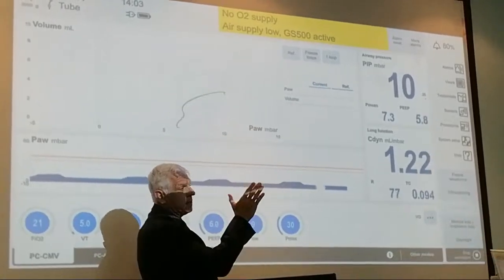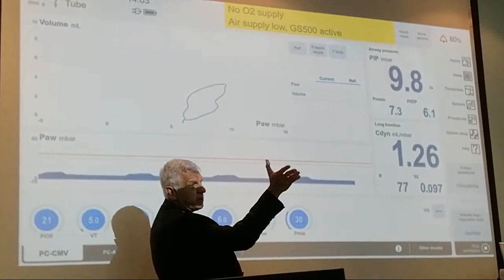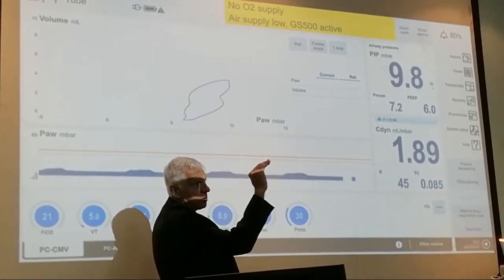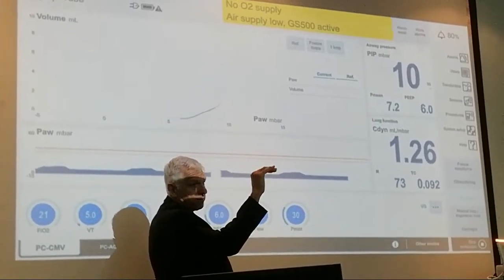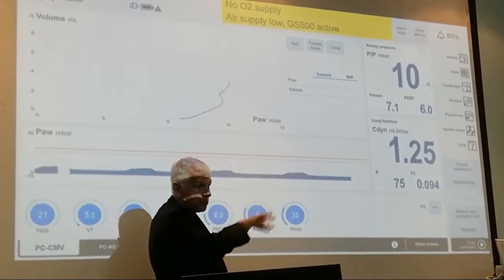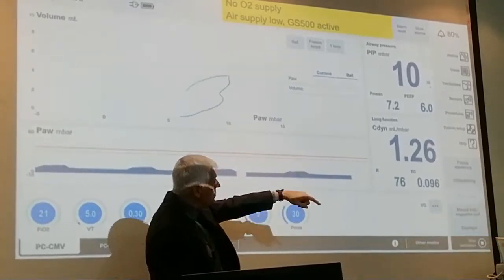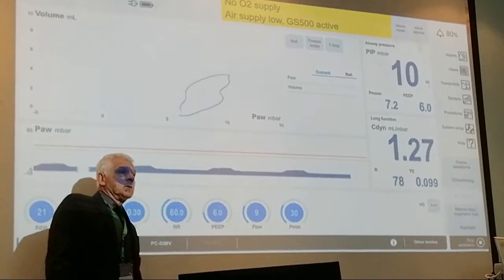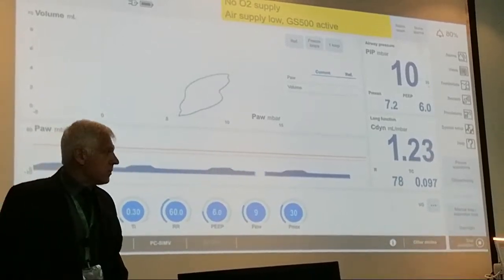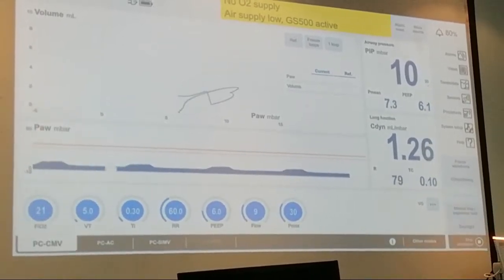You get to a point where you're increasing the pressure without getting volume. So the last 20% of the compliance curve is significantly lower than the rest of the compliance. So your C20 versus C may be very low. In that case, you may need to do something about it. Okay, let's make it worse and see if we can do that.